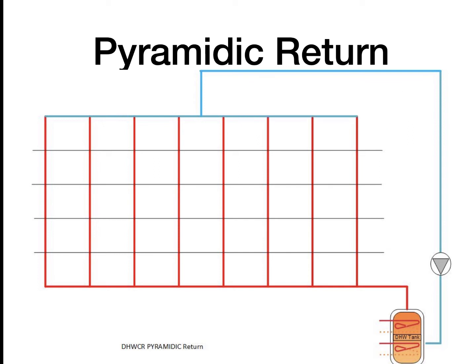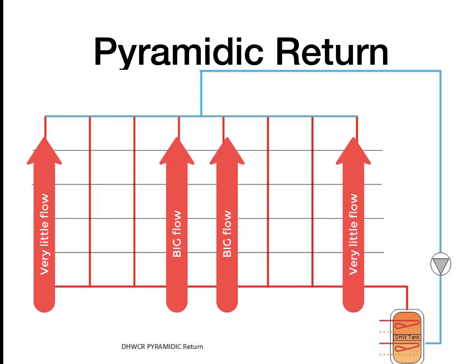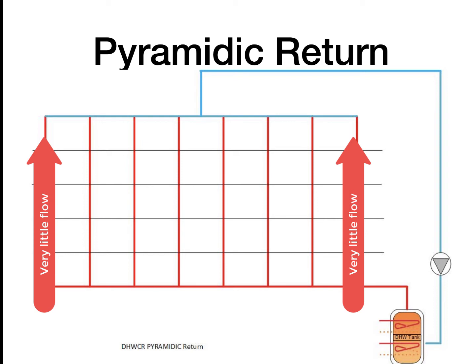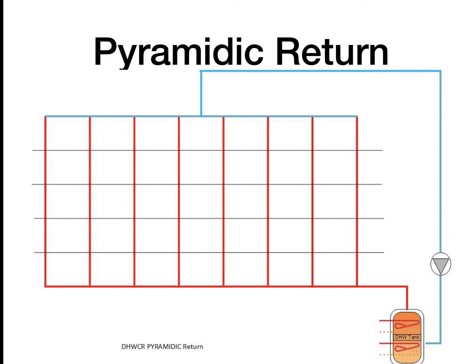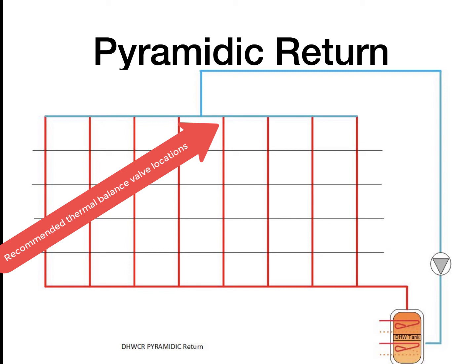The problems of imbalance should be pretty obvious. Water being wet, lazy, and stupid is going to follow those paths, which are the path of least resistance, which would have a tendency to be essentially the middle third of the risers within that picture itself. The outer edges on the left and the outer edges of the risers on the right are going to have a tendency to have poor flow, and consequently the people will be complaining about no instantaneously available hot water. This is without a doubt the least preferred method of piping a domestic hot water circulation return system, but again, it can be corrected with the Caleffi 116 series thermal balancing valves.